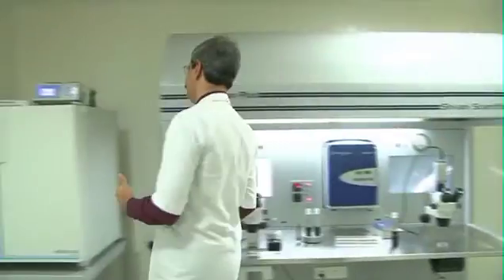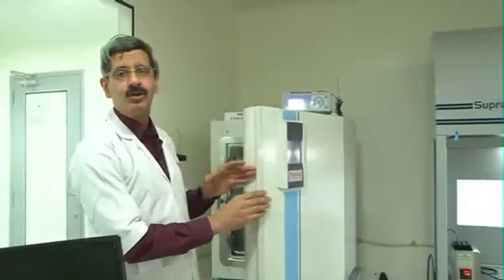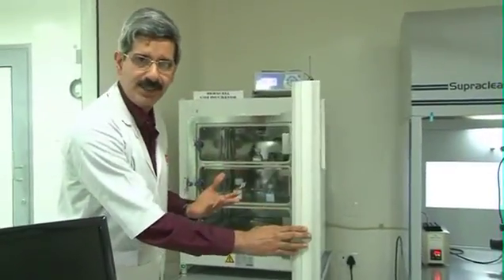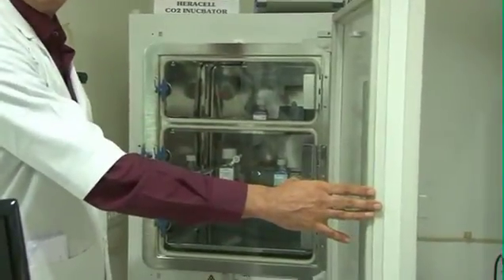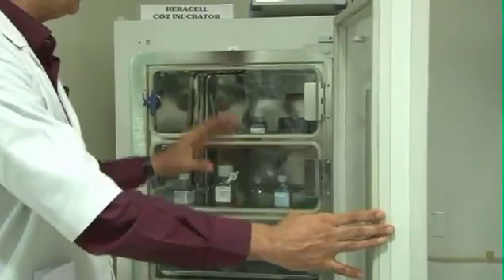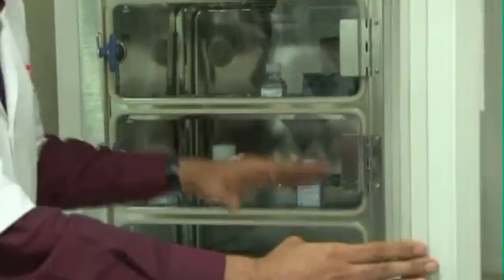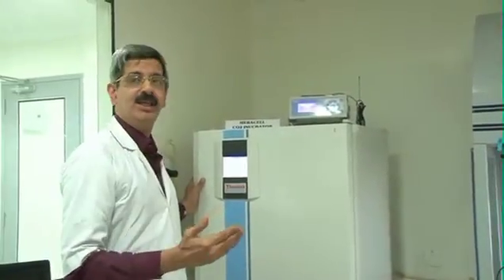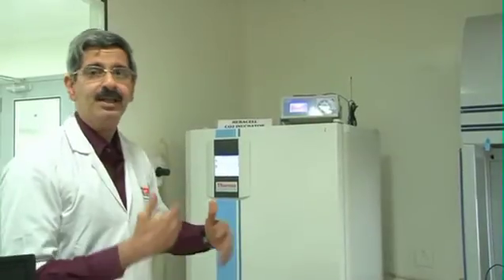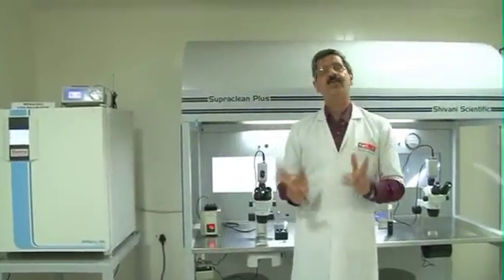These are water-jacketed CO2 incubators; there are also available triple gas incubators with compartmentalized three-door paneling for easy access, making the embryologist's life simpler by allowing compartmentalization of products. These are ideal for culturing gametes, equilibration of media, and subsequent day-to-day procedures. The laminar flow is also an ideal tool for dish changing, media changing, and media washing.